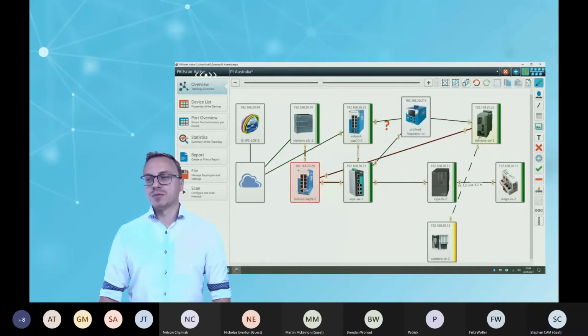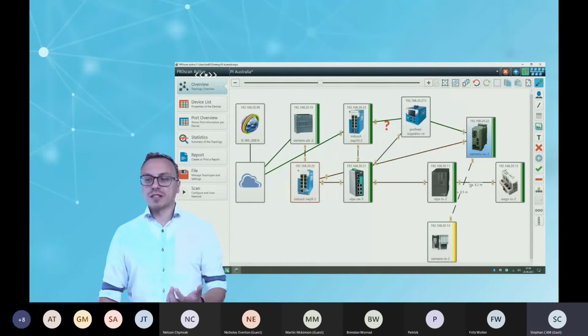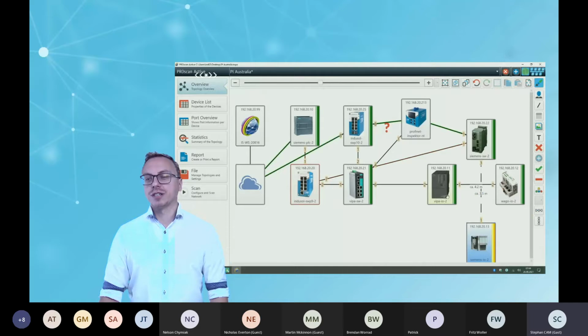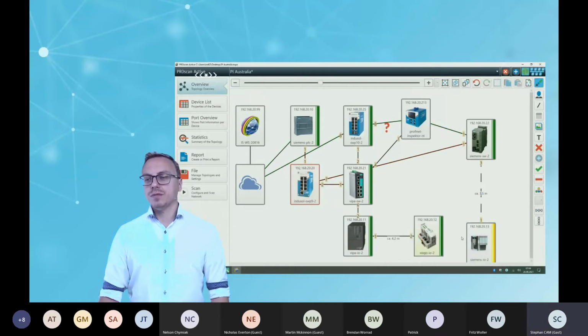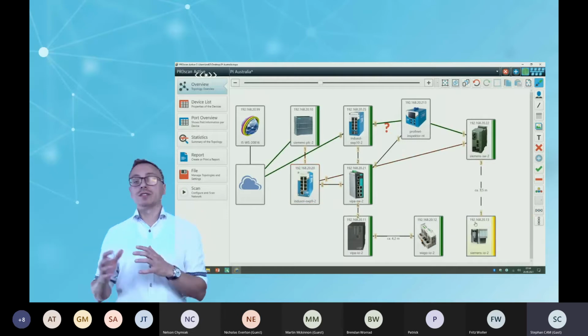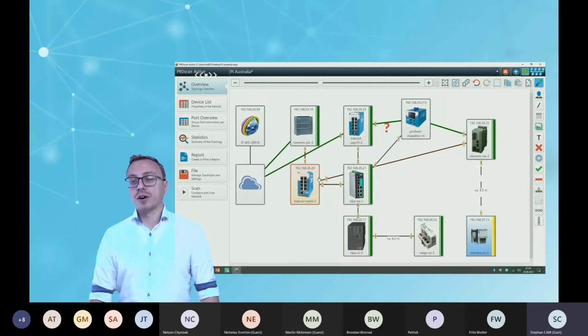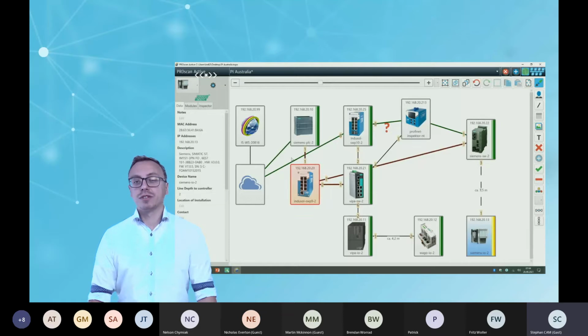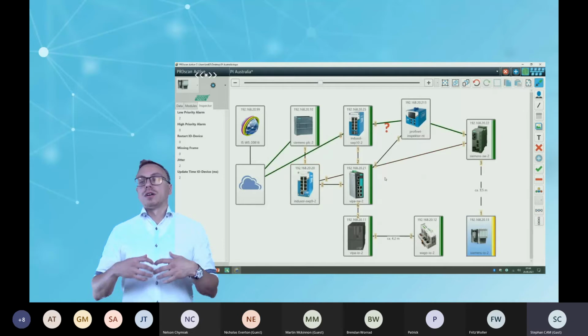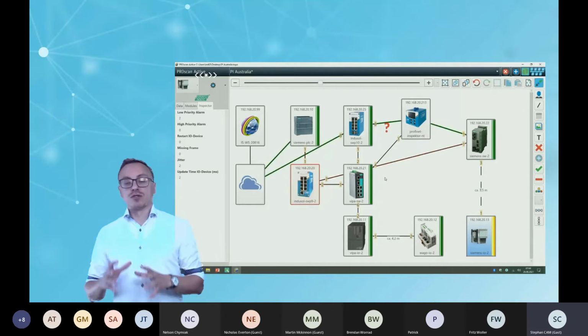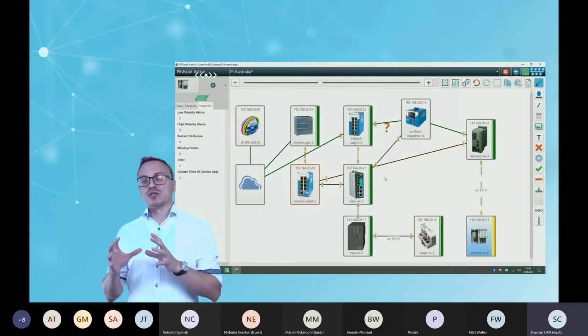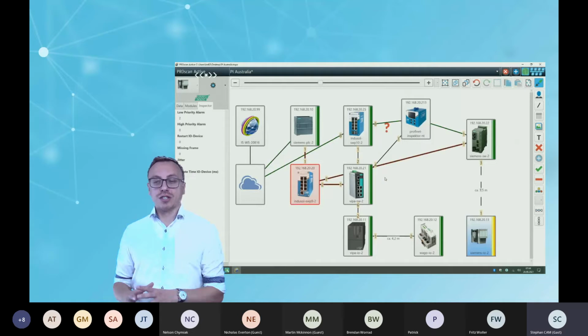It looks now a little bit strange, but as I said, this software will show you all your changes in your system. So if you want to know what the reason of this issue is, first of all, you can find out, okay, here you see the wiring was changed in the past. And for example, why you have yellow bar charts here, you can press on the device, go to the inspector overview, and you see here now we have low priority alarms. So this software helps you to analyze your topology, and to find out in your topology what or where the issues are and what changed over time.